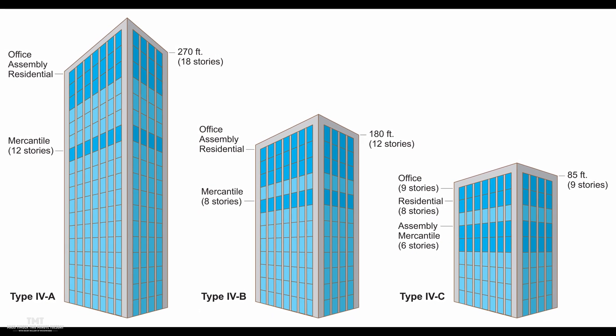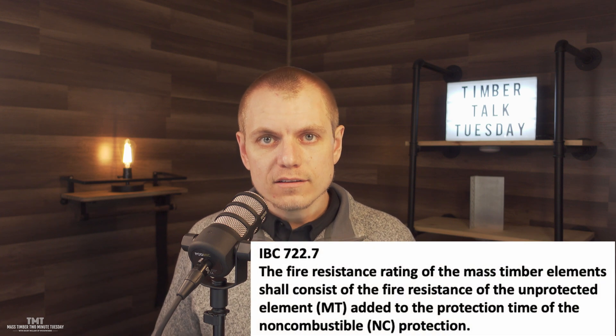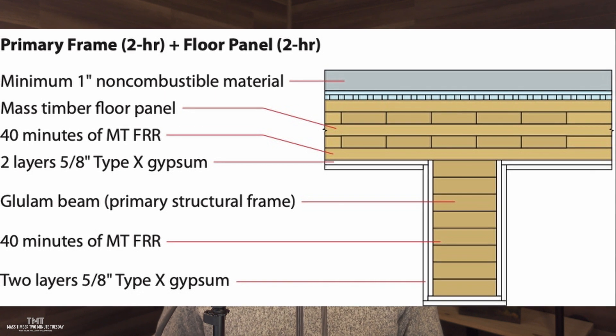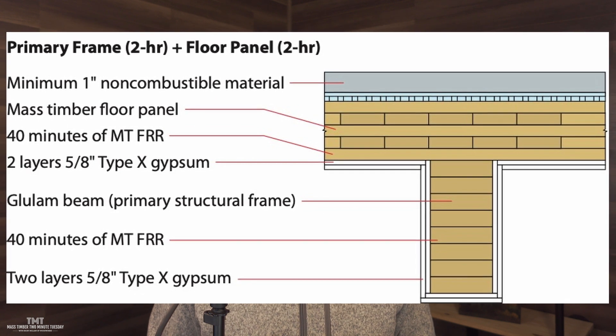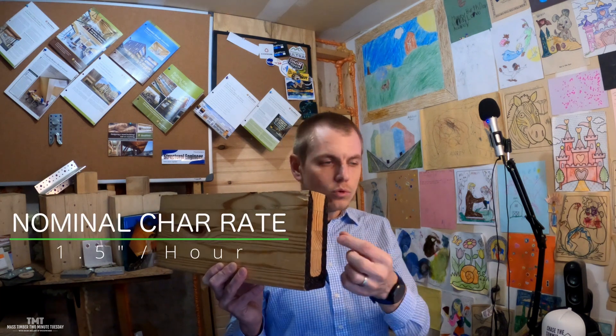This is certainly done in the new tall mass timber construction types where in Type 4A and 4B the code requires timber encapsulation. You're actually using that timber encapsulation as a minimum two-thirds of the required fire resistance rating of that element. For example, in a Type 4B building with a floor beam that has a two-hour fire resistance rating requirement, if we're encapsulating that beam we need to get two-thirds — or 80 minutes — of that two hours through non-combustible layers. Usually that's going to be two layers of 5/8-inch Type X gypsum wallboard.